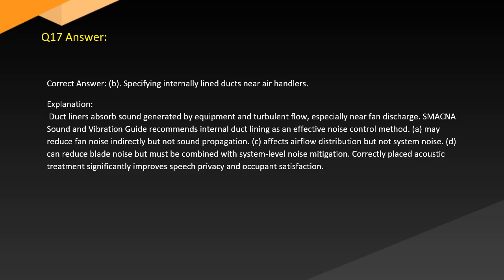Answer. Correct answer B. Specifying internally lined ducts near air handlers. Explanation. Duct liners absorb sound generated by equipment and turbulent flow, especially near fan discharge. The Smacna sound and vibration guide recommends internal duct lining as an effective noise control method. A. May reduce fan noise indirectly but not sound propagation. C. Affects airflow distribution but not system noise. D. Can reduce blade noise but must be combined with system-level noise mitigation. Correctly placed acoustic treatment significantly improves speech privacy and occupant satisfaction.